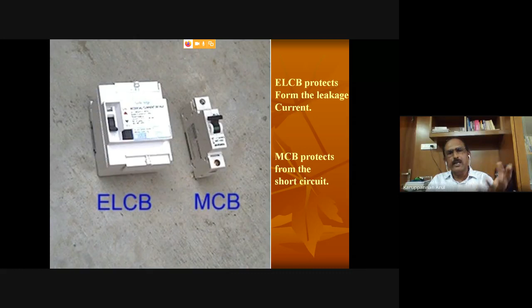What does ELCB mean? Earth leakage circuit breaker. It has a function of overload protection as well as earth leakage protection. If anybody touches and gets a shock from any equipment, and the earth current passing through our body is more than 15 to 20 milliamperes, this earth leakage circuit breaker will trip off the entire supply to the house. So it is a very safe mechanism.